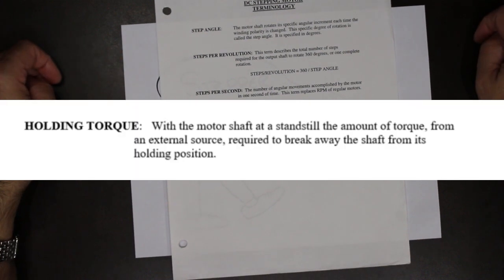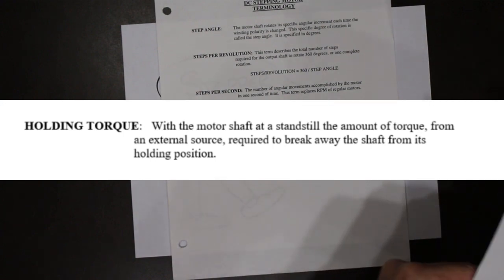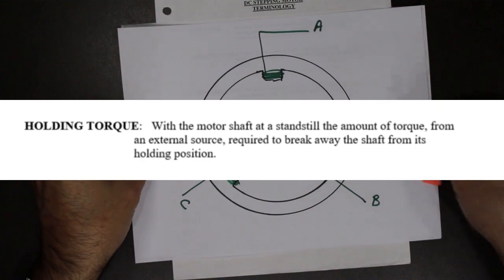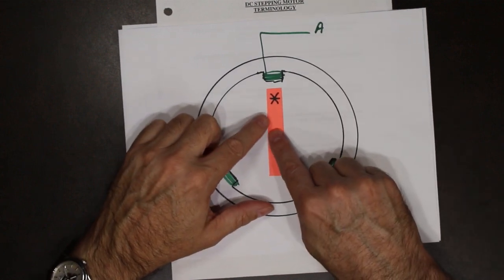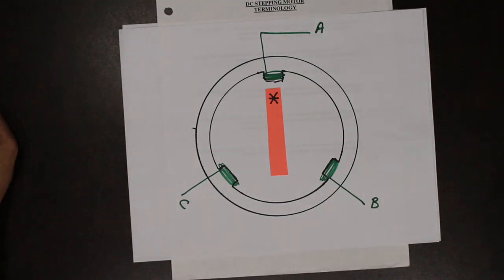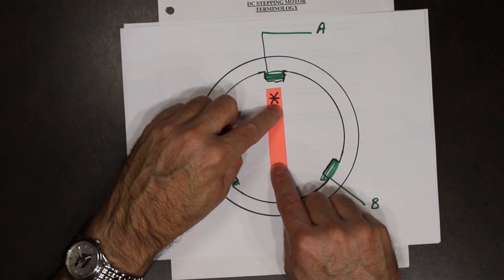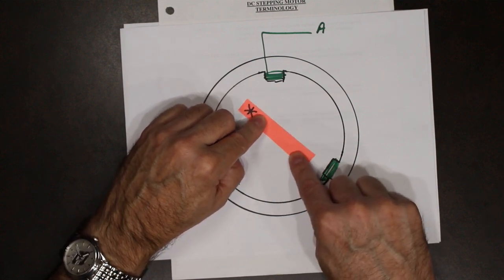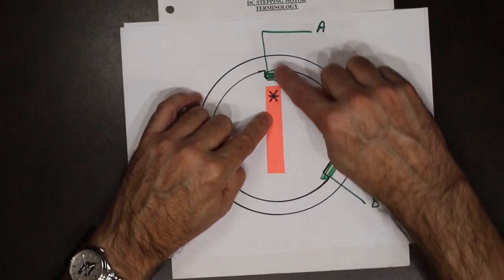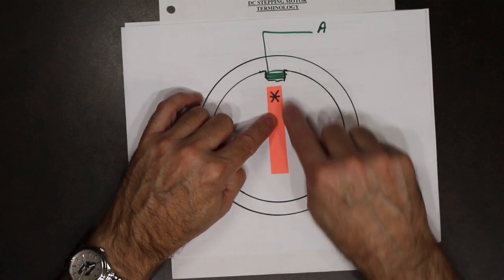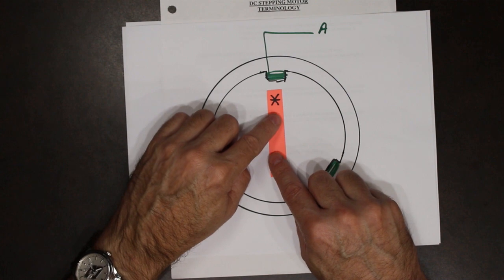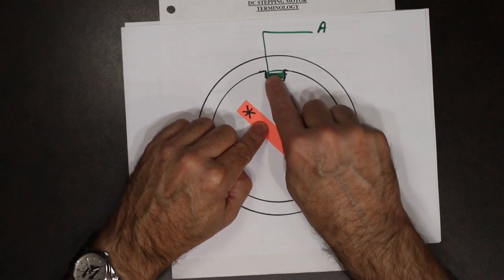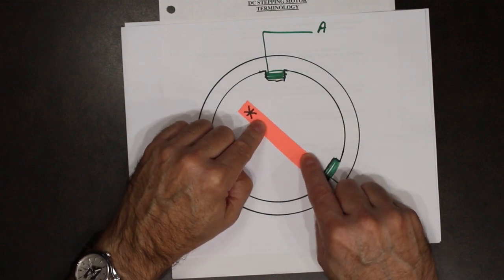The next term is holding torque. With the rotor at a standstill and the pole still energized, how much torque is required to break it free? If I energize pole A and lock the rotor into that position, the pole becomes a magnet and the rotor is attracted to it. How much force would I have to put on the rotor to actually overpower that magnetic field? That's what's called holding torque.